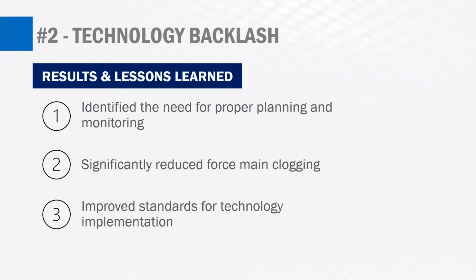So as a result, it was identified that there needed to be proper planning and monitoring in place when this new technology was going to be introduced to these pumping systems. The planning was done actually fairly well. The one key here was that the controls logic needed to be ironed out in more detail, making sure that scour velocity was going to be achieved at least once or twice per day. But really, the monitoring is the key here. It would have been best if routine monitoring was being done to verify that scour velocity was being met.